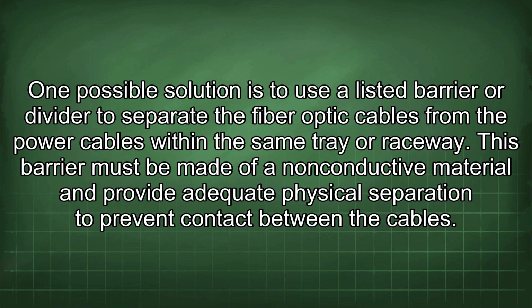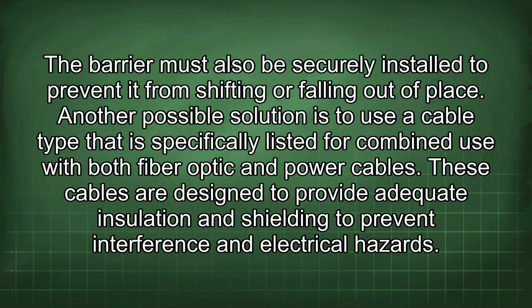One possible solution is to use a listed barrier or divider to separate the fiber optic cables from the power cables within the same tray or raceway. This barrier must be made of a non-conductive material and provide adequate physical separation to prevent contact between the cables. The barrier must also be securely installed to prevent it from shifting or falling out of place.